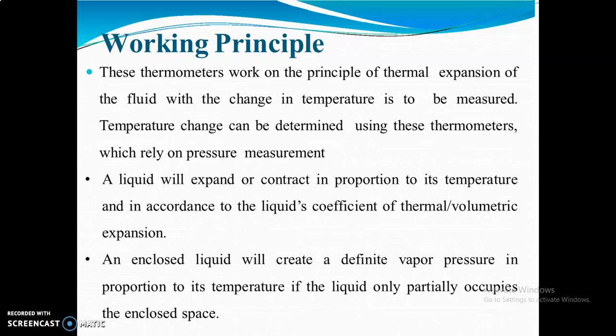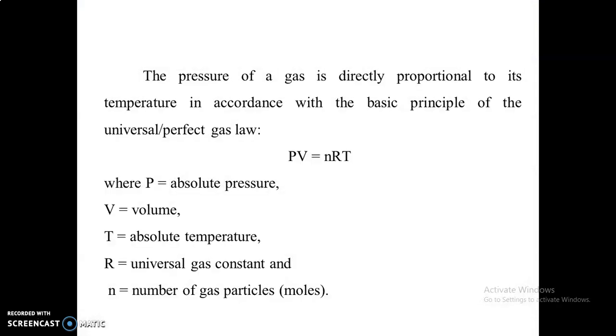For pressure measurement, we use the Bourdon tube. The liquid will expand or contract in proportion to its temperature in accordance with the coefficient of thermal expansion. An enclosed liquid creates a definite vapor pressure in proportion to temperature. The pressure of gas is directly proportional to temperature, following the basic gas law: PV = nRT, where P is absolute pressure, V is volume, T is absolute temperature, R is the universal gas constant, and n is the number of gas particles.